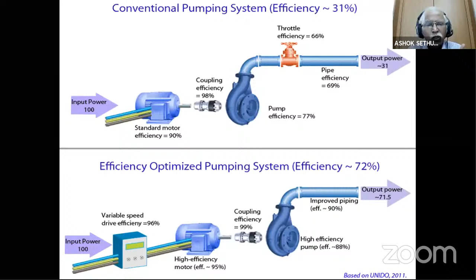The government or the industry thinks that by replacing the pump, I am achieving the energy savings. It is not so. You can achieve the energy savings when you replace the pump and the piping. Changing the pump itself, you can increase efficiency by 10 to 20%, but the piping also gives a lot of energy savings, about 20%. A typical 7.5 HP pump is replaced by a 5 HP pump, and instead of a GI pipe, it goes for white PVC pipe. The energy savings possible is almost 48%.